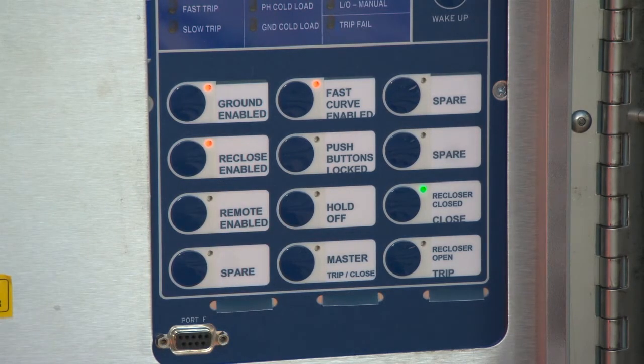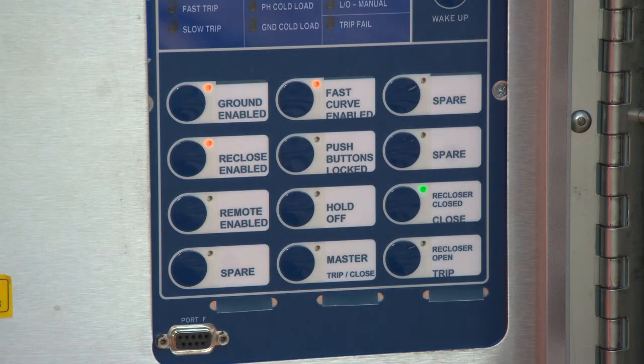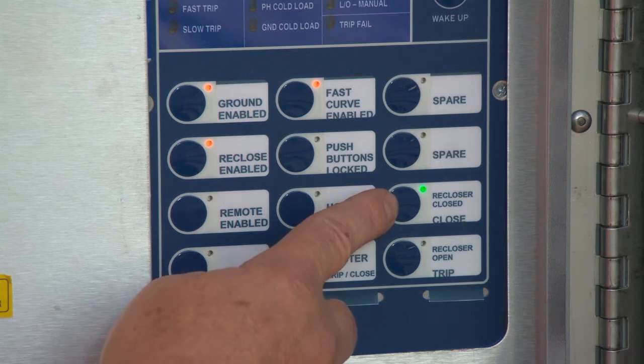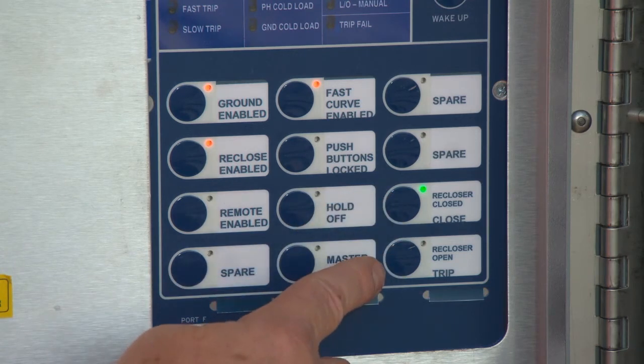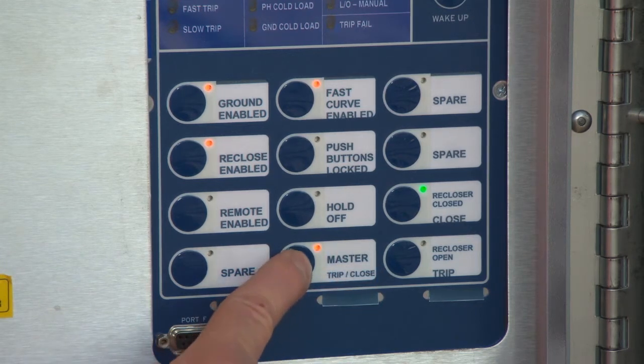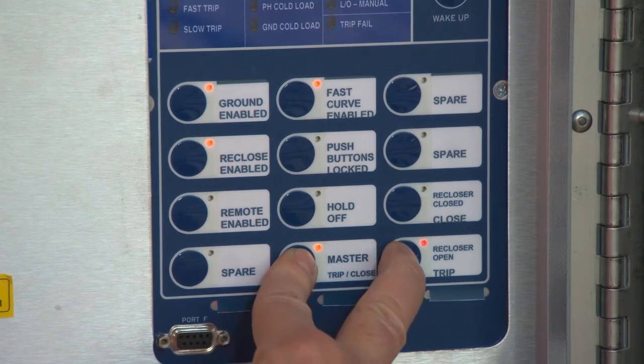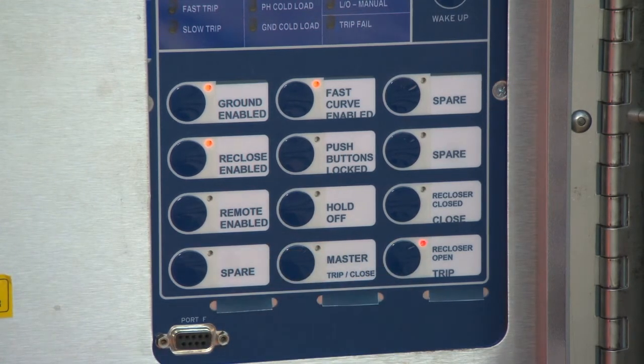There are 2 spare buttons on the right side of the unit. These are currently not programmed. Finally, we have 2 buttons: the Recloser Closed, which is currently green, and Recloser Open Trip button. In order to change the state of the recloser, you must push the master button and the trip button simultaneously. The recloser will now trip open. The LED will turn red.